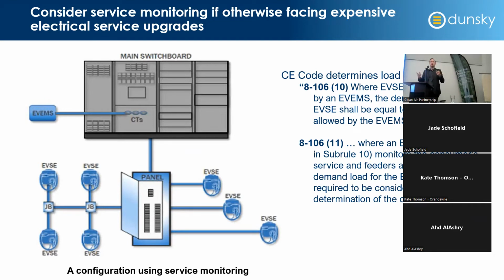Now, the Canadian Electrical Code is inherently really conservative. Multifamily buildings are pretty much always using maybe 30, maybe 50% of the actual electrical capacity at their absolute maximum, so there tends to be a lot of spare capacity. The vast majority of the time, you design for the ability to use service monitoring, but you'd never actually need it because there's tons of spare capacity in the building that can handle those additional EV loads.